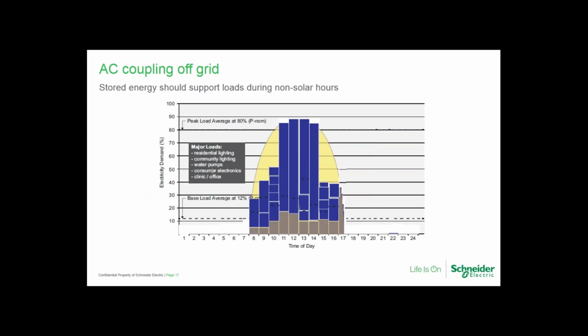Now, if we move all those loads into solar hours, then absolutely we're getting much better efficiency, because that power is passing directly to the load. In other words, we're not storing the energy. That's where the efficiency advantage of AC coupling takes a bit of a nosedive.